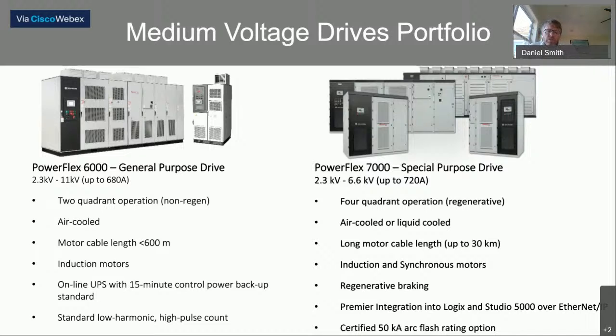Our second drive is the PowerFlex 7000 platform. This platform has been around for a few years now, and it's just been a robust platform. We like to consider this our special purpose drive, and it has a rating from 2,300 volts all the way up to 6.6 kV, and an amp rating of 720 amps. This drive is a current source drive, which makes it a little different than the PowerFlex 6000. You can get it in a liquid cooled option or an air cooled option.